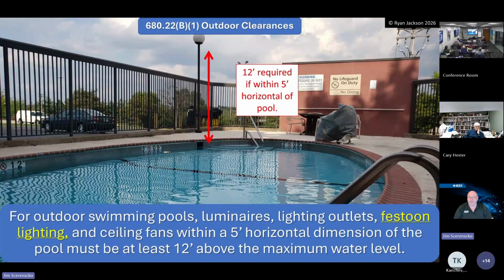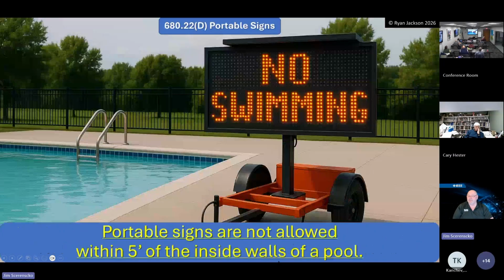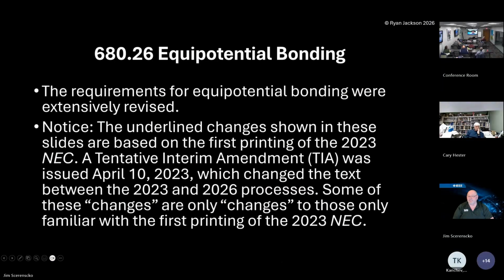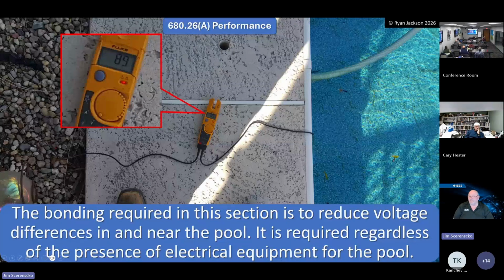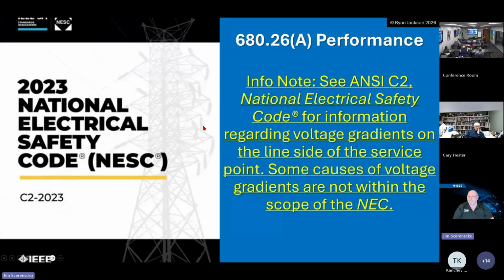Lighting, festoon lighting, we see a lot more of this decorative lighting that's hanging all over the place, so they added the word festoon in there. Portable signs are not allowed within 5 feet. The equipotential bonding grid around the pool. The bonding requirements section is to reduce the voltage differences in and near the pool. You're not grounding the pool, you're bonding all the metal parts together.